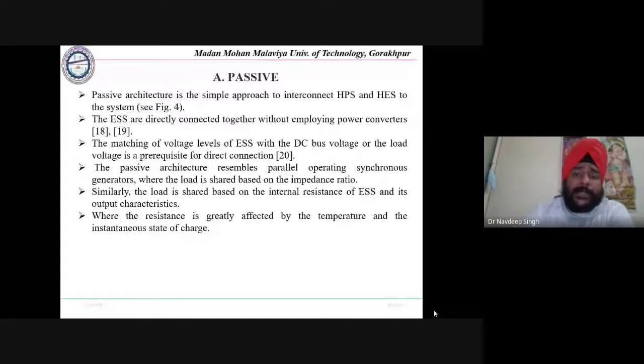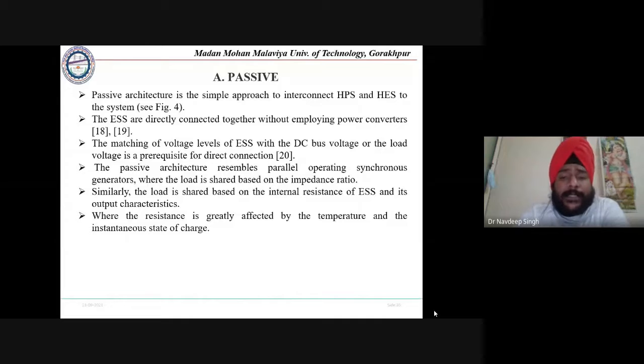The load is shared based on the internal resistance of the ESS and its output characteristic, where the resistance is greatly affected by the temperature and the instantaneous state of charge. If we increase the temperature, and the instantaneous state of charge is high, losses will be more in the resistance. There is more power loss and more voltage drop across the resistance, so the efficiency of the system is reduced when we put in a high resistive system.